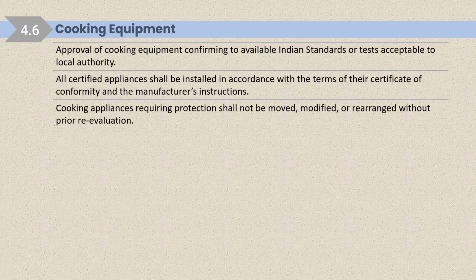Cooking appliances requiring protection shall not be moved. This happens. You will see inside the kitchen. Suppose initially some equipment was placed just below the exhaust hood, but with time, due to space constraints, they used to shift their equipment outside the hood. That may result in fire, or also the grease accumulation can be on the ceiling or any other places.